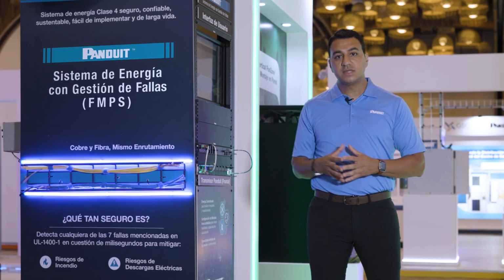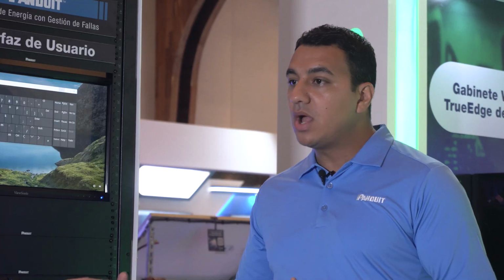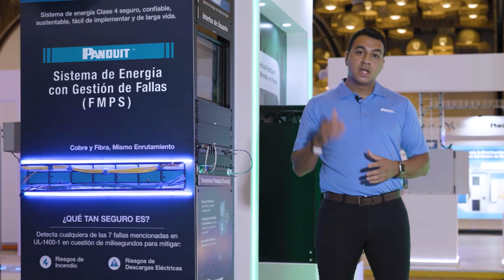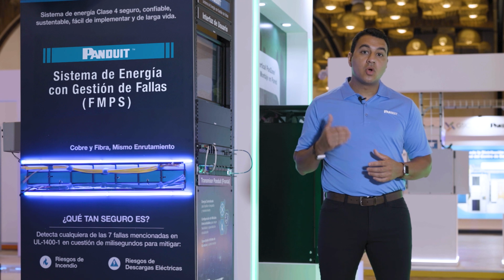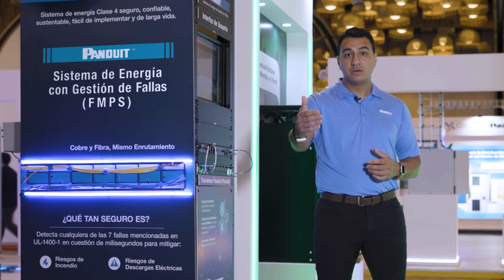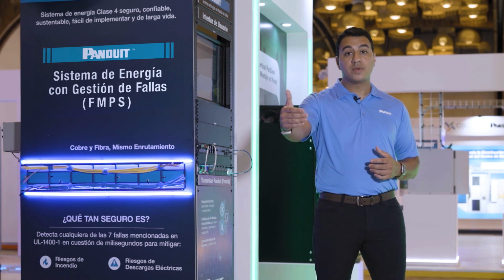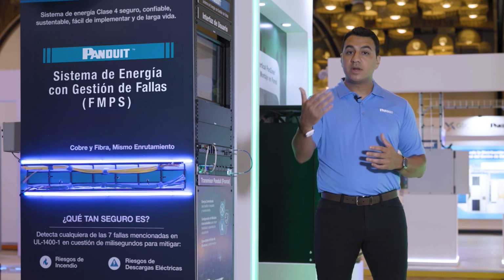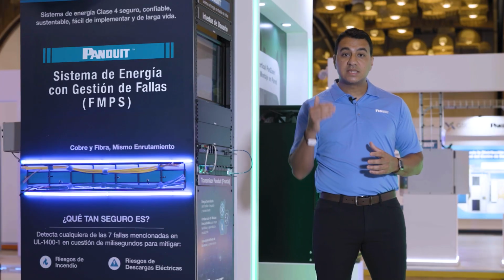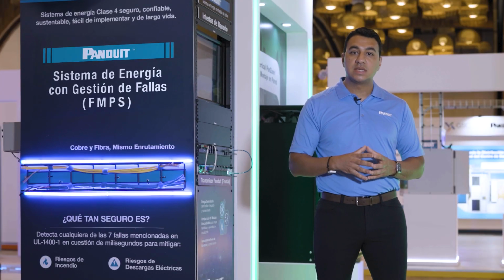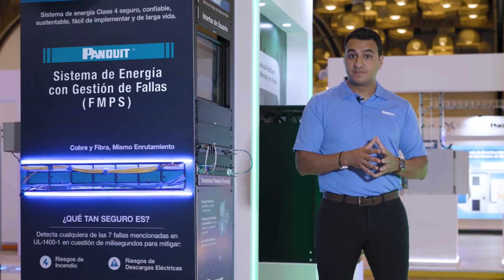So our Class 4 system is pushing 360 volts from the source. This high voltage allows you to go really long distances with the power. Our system can push up to 2 kilometers away. There is no limit on the power, but our system can push 600 watts per copper pair, so you get significant power over long distance, safely and efficiently.